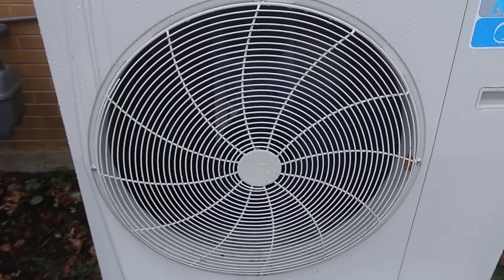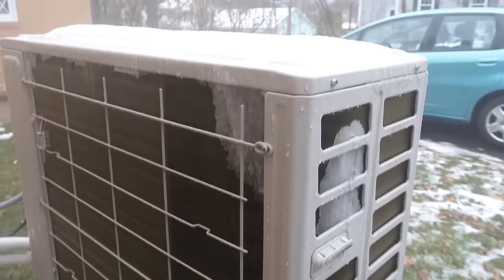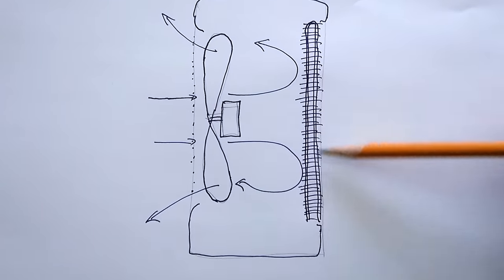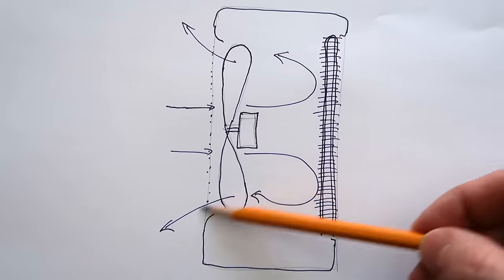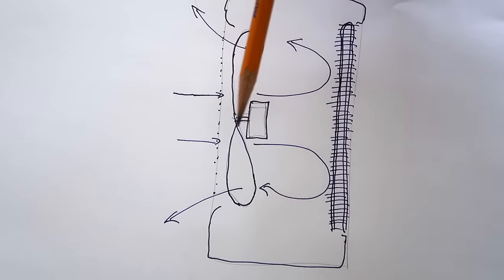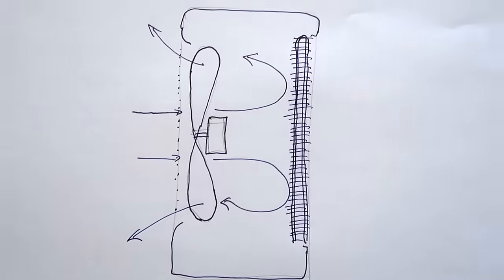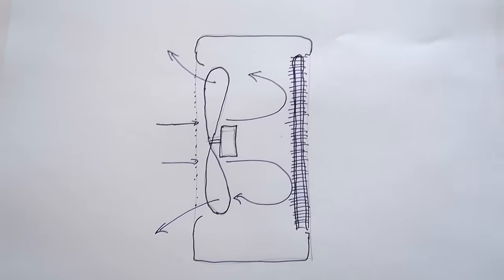And most of the ice is gone by now. And it's starting to turn on the fan. I don't really want that, so I think this is enough de-iced. I'll just turn it back into heating because now we're just throwing away heat. But surprisingly the performance of the unit in terms of heat output per energy used before and after that defrost wasn't that much different. So I think what happens is even if these coils are completely blocked up with ice, the centrifugal force of the fan and such makes it much more effective around the edges to blow air out. And of course air has to come in. It comes in at the middle of the fan where the blades are moving slowly and basically going past the coils and it's extracting heat that way. Not nearly as effective as sucking air through but still getting some heat from the outside.